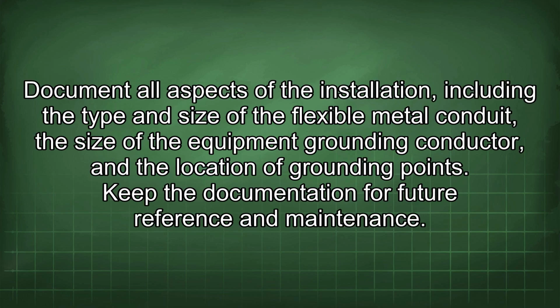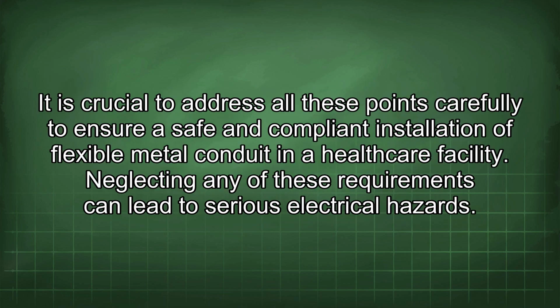Document all aspects of the installation, including the type and size of the flexible metal conduit, the size of the equipment grounding conductor, and the location of grounding points. Keep the documentation for future reference and maintenance. It is crucial to address all these points carefully to ensure a safe and compliant installation of flexible metal conduit in a healthcare facility. Neglecting any of these requirements can lead to serious electrical hazards.